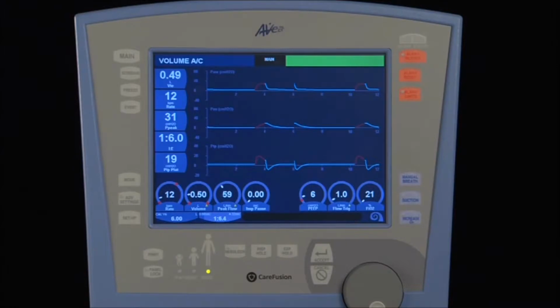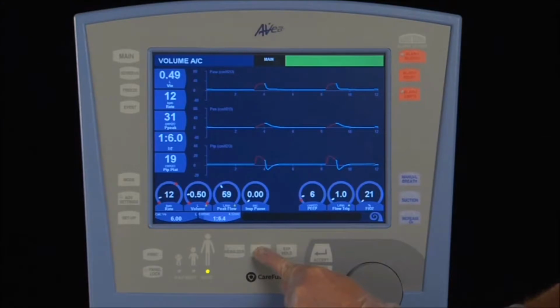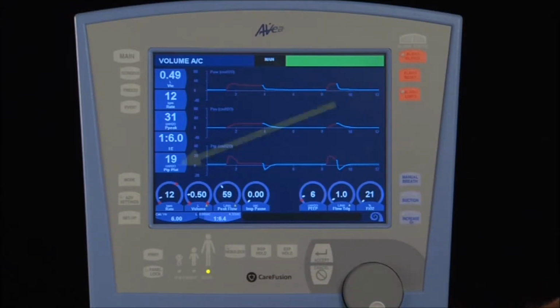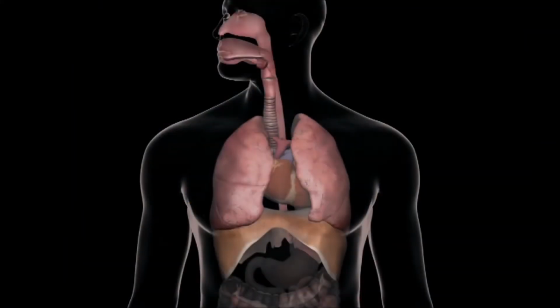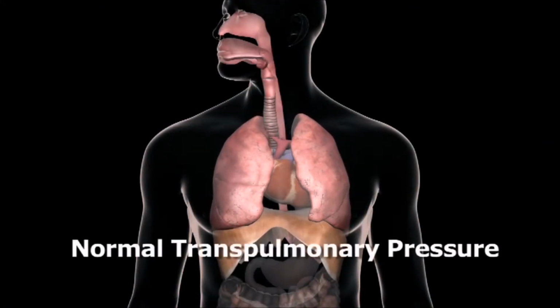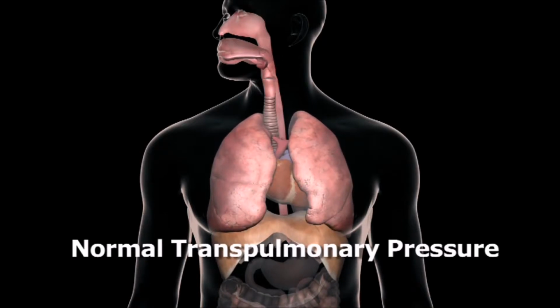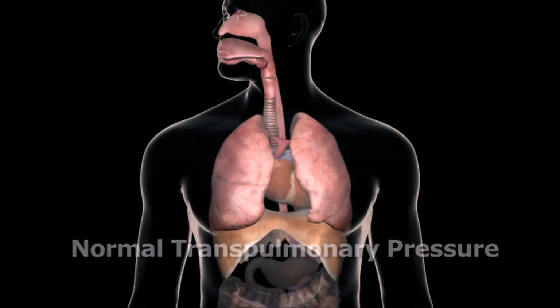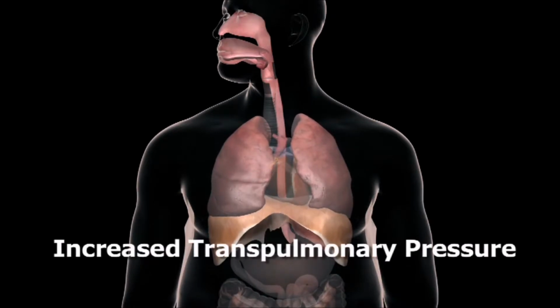To obtain the transpulmonary plateau value, depress the inspiratory hold until a static plateau is identified on the pressure scalar. The value will remain in the monitor window for 15 minutes. If the operator feels this is not a valid measurement, they may want to repeat the maneuver to confirm accuracy. When monitored correctly, transpulmonary pressure plateau may more accurately indicate lung inflating pressure, independent of resisting forces. Literature suggests protective lung strategy guidelines should keep transpulmonary pressure plateau less than 20 centimeters water at maximum.